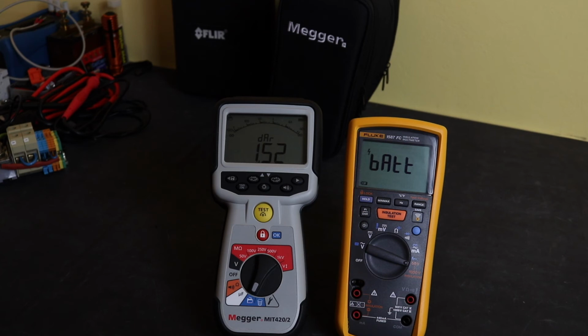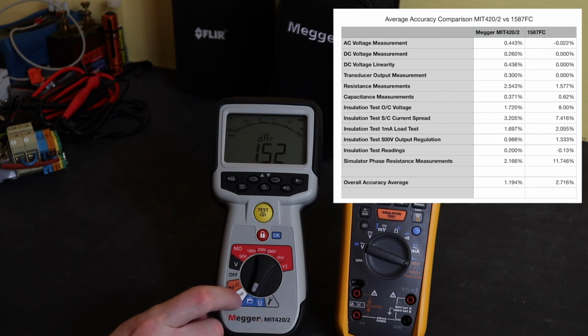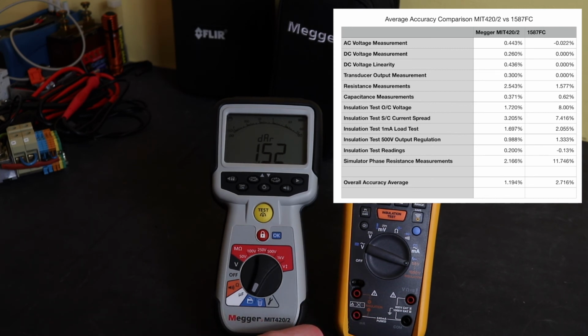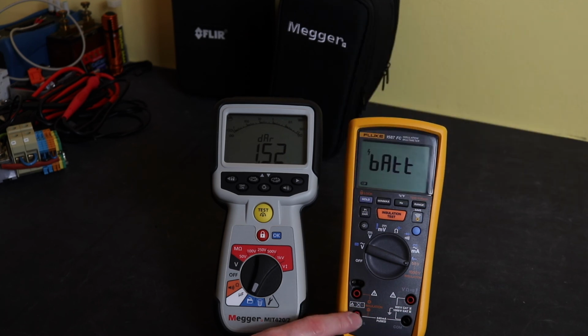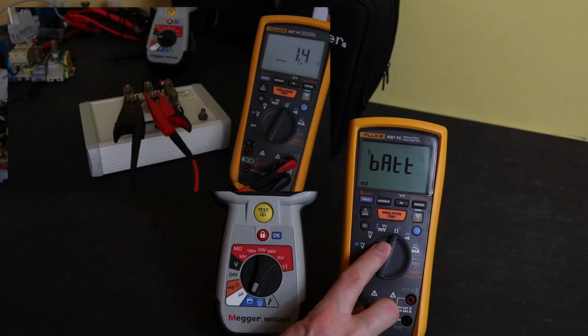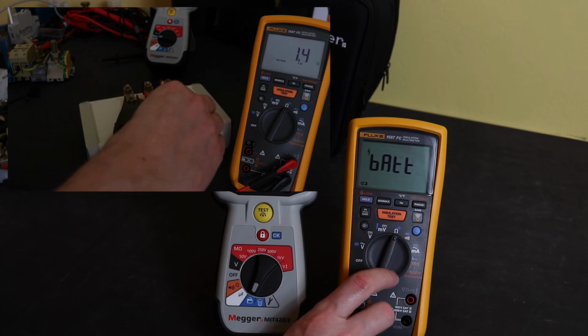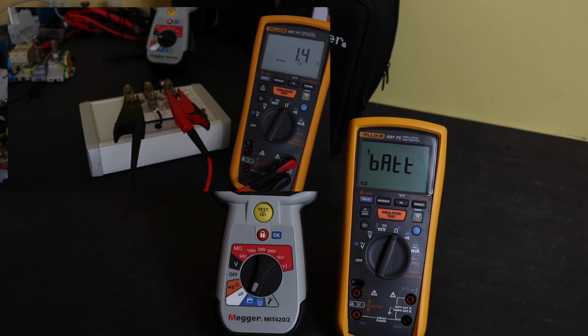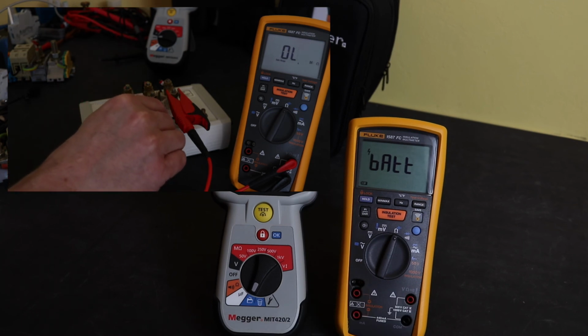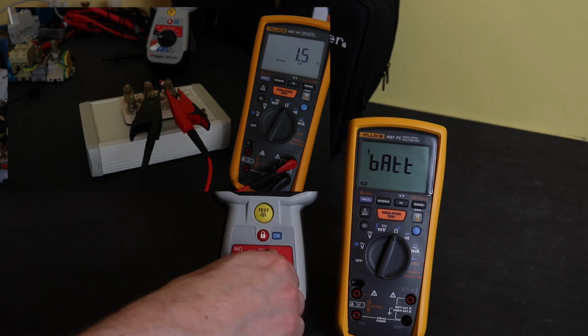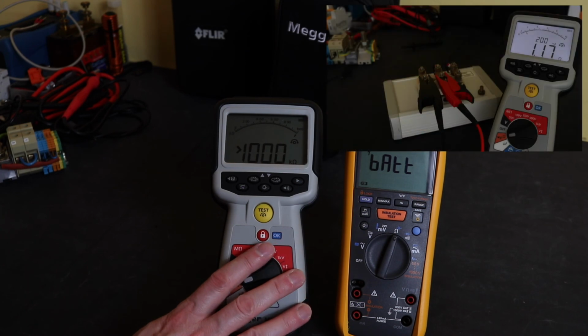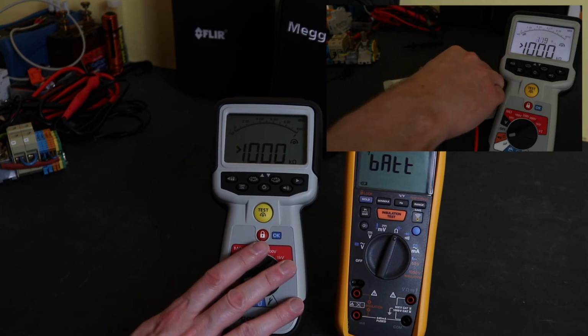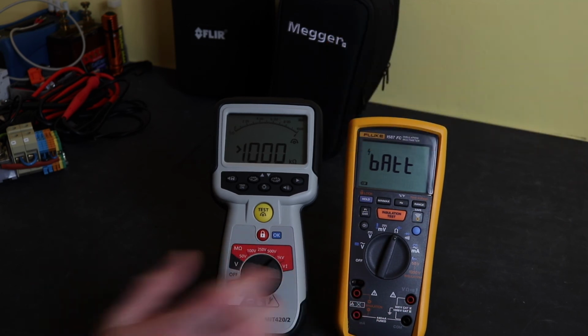In terms of accuracy, for overall accuracy, again I'll put the table up. In actual fact, the accuracy score goes to the Megger at 1.194% against 2.716% for the 1587FC. Where the 1587 loses most of the points is on the winding resistance test on my little simulator. The ohms reading is very poor, only 1 decimal place resolution, no 200 milliamp test current, and the tests against the phase resistance readings on the winding simulator come out quite bad. Whereas the Megger has an extra decimal point of resolution coupled with a 200 milliamp test current, and you get much more accurate readings, and that's where the biggest difference is between the two instruments.